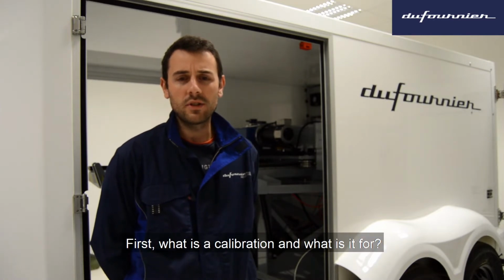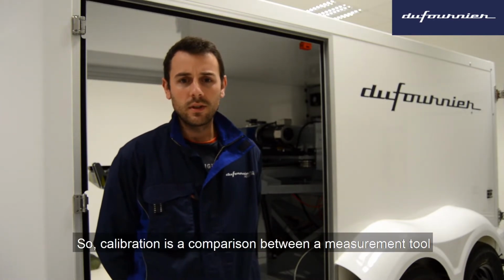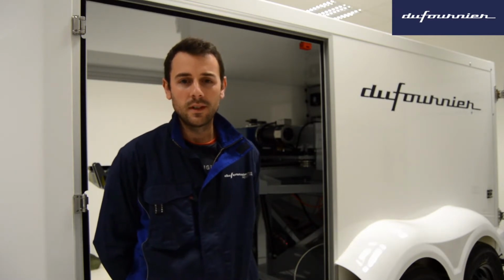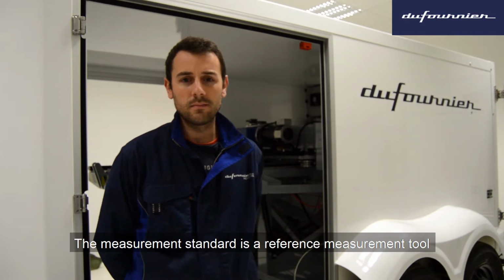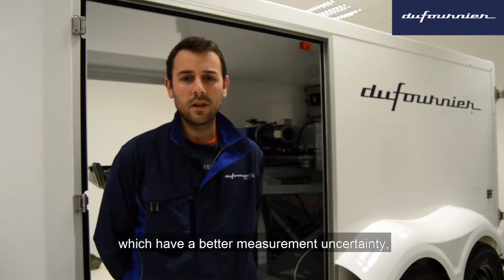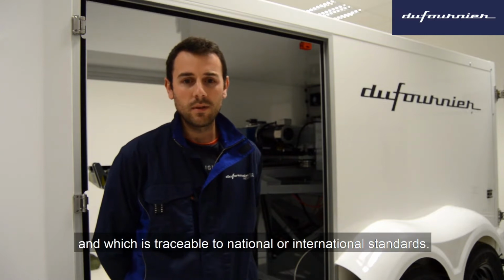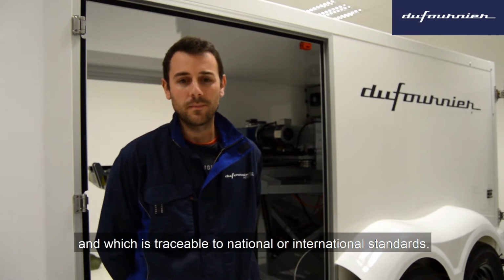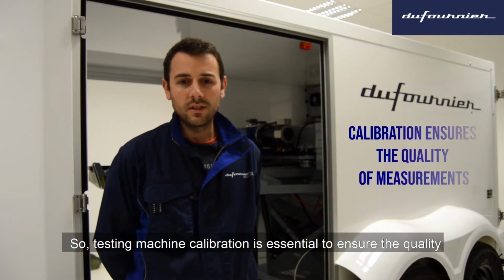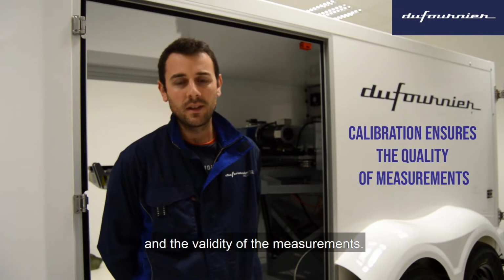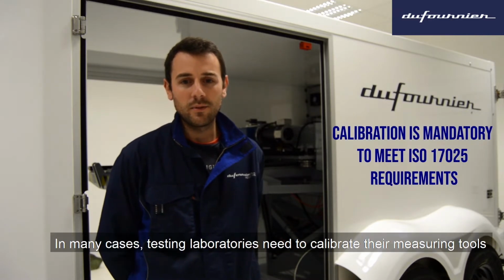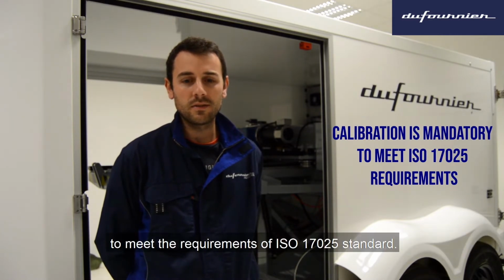First, what is a calibration and what is it for? So, calibration is a comparison between a measurement tool and a measurement standard. The measurement standard is a reference measurement tool which has a better measurement uncertainty and which is traceable to national or international standards. So, testing machine calibration is essential to ensure the quality and the validity of the measurements. In many cases, testing laboratories need to calibrate their measuring tool to meet the requirements of ISO 17025 standard.